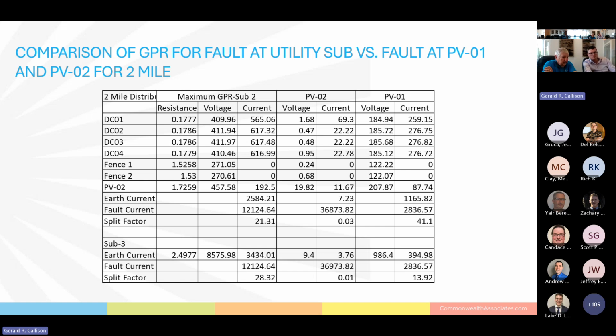And the earth current at the utility substation was about 2.5, or the resistance, I'm sorry. But the current is about 3450, and the voltage was just a little under 8600. Okay, so if you look at these voltages and compare them to a fault on the low side of the distribution transformer at the collector station, you can see that the fault current is much, much higher, about 3 times higher than it was for a fault at the utility.